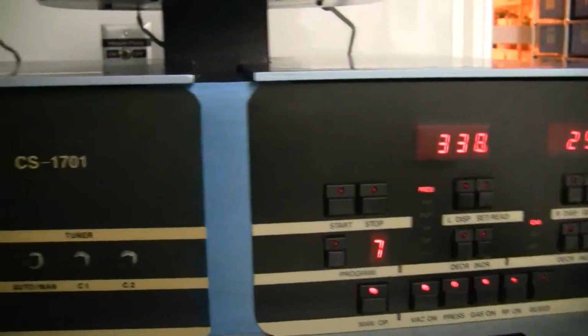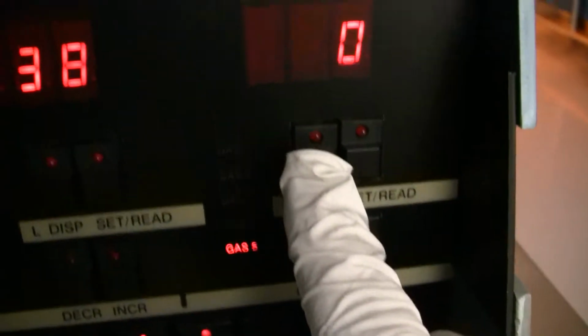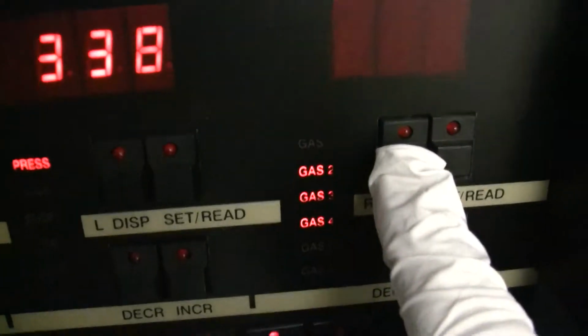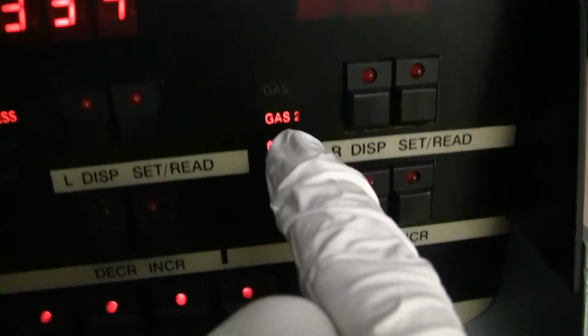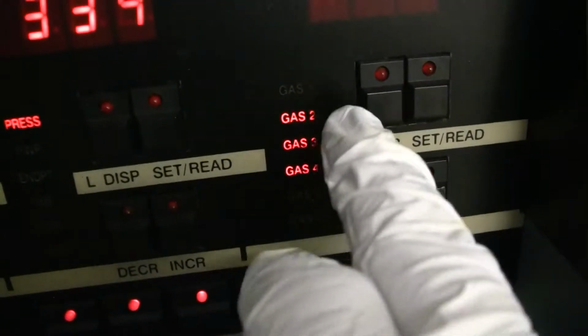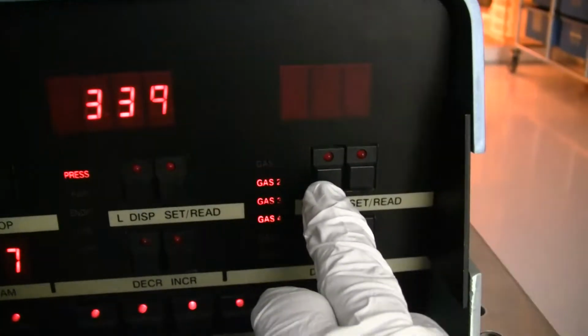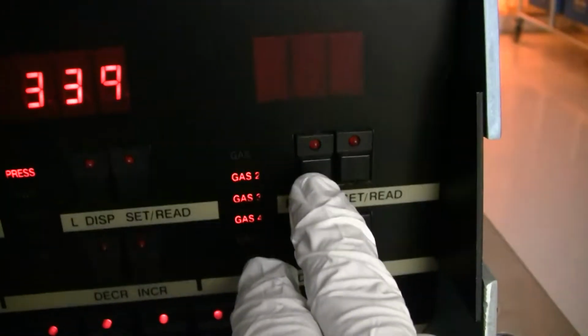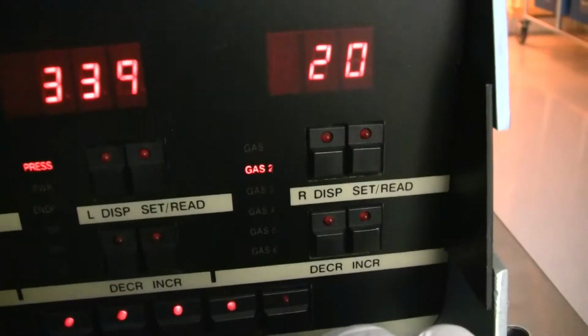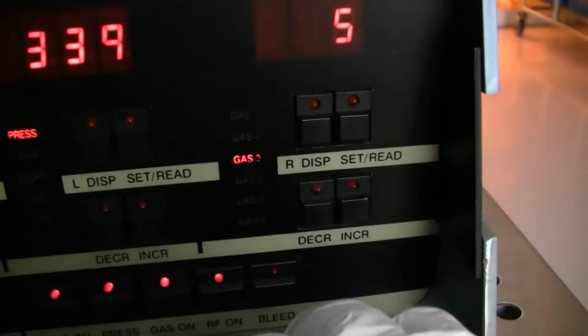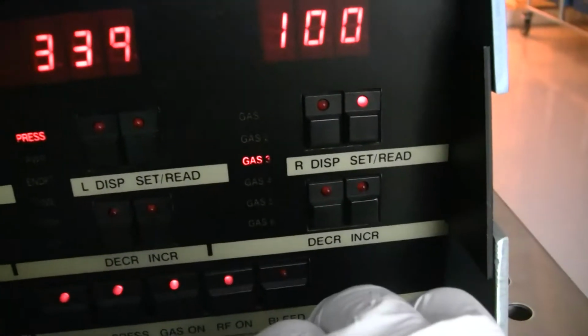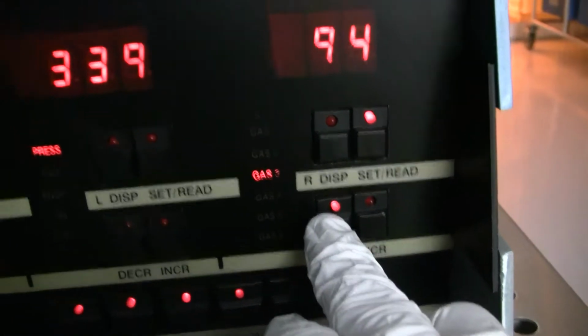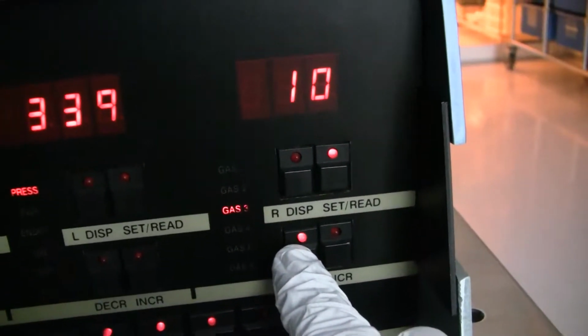I really don't think the oxygen should have any purple in it. It's a bit disturbing. Let me go through and check these again. Oh, so according to this, when you get to the bottom of the list, it'll show which gases have a non-zero set point. So hopefully that's in focus. Okay, so let's see. So gas 2 is oxygen, 20%. This gas, 100%.